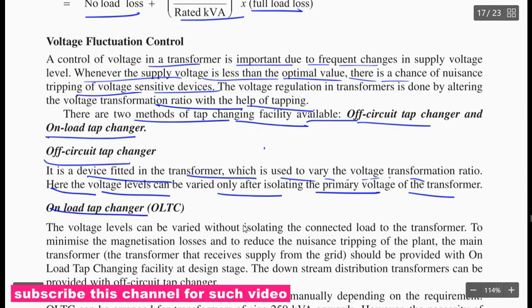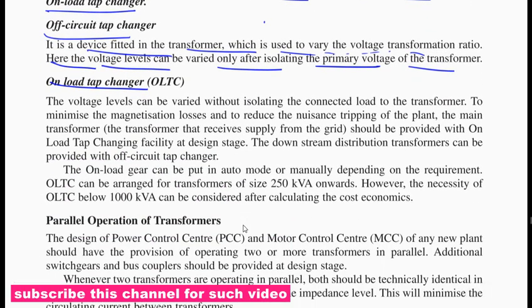Next, let's talk about the on load tap changer. The voltage level can be varied without isolating the connected load to the transformer, to minimize the magnetizing losses and reduce the nuisance tripping of the plant.